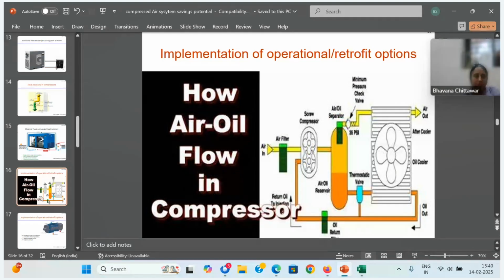So what I did, step by step, I put an orifice plate and restricted by 5%, 10%, 20%, 30%. I recorded a lot of parameters, and a lot of studies happened. I shared them with some of the suppliers. And incidentally, this gave a good amount of savings, but there was a negative thing also. Due to less oil circulation, sealing reduced. Then compression efficiency went down, but power came down. Specific power consumption came down. Ultimately, we are bothered only about specific power consumption, kilowatt per CFM or kilowatt per meter cube. So we have achieved that actually.